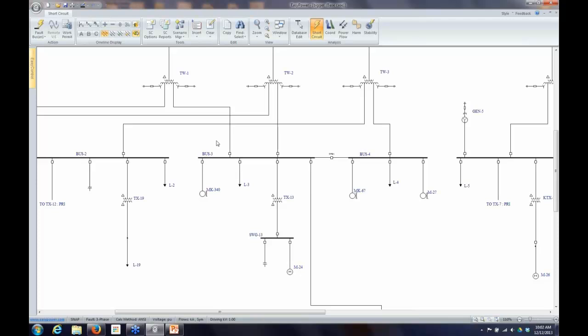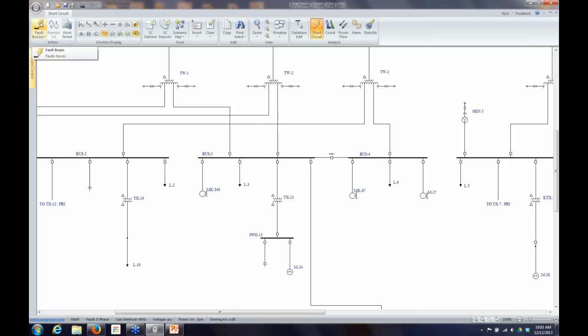Short circuit calculations are done on a per bus basis, regardless of whether you fault every bus or just one. EasyPower faults one bus at a time and does it really fast, so it seems to all be happening at once. I can control how many buses I fault — that's determined by what buses, MCCs, or panels I have selected when I click Fault Buses. If I have nothing selected and hit Fault Buses, it will fault every bus.